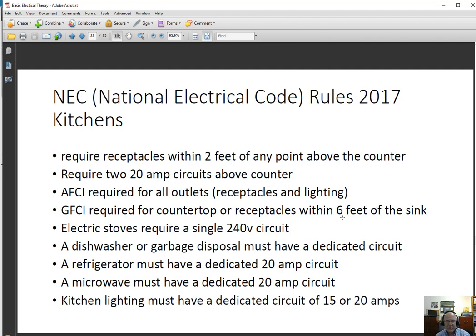Other NEC requirements: electric stoves require a 240 volt circuit. If you have a built-in dishwasher or garbage disposal, each must have a dedicated circuit — they can't be on the same circuit as the two small appliance circuits above the counter. A refrigerator must have its own dedicated 20 amp circuit. The reason is to protect your food from spoiling: if your refrigerator is on the same circuit as a small appliance circuit, and you blow that breaker with your Belgian waffle maker and toaster oven, your refrigerator stops working. If you don't notice it, the food all spoils.